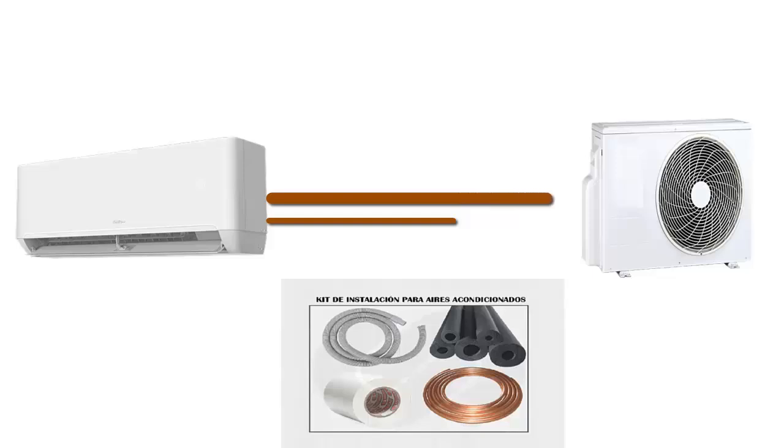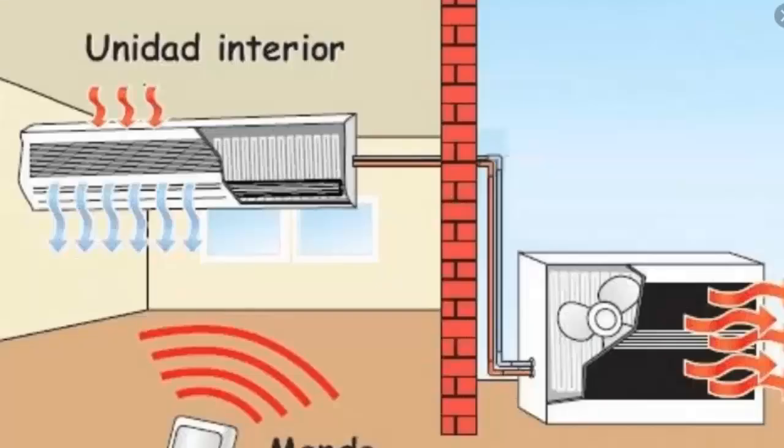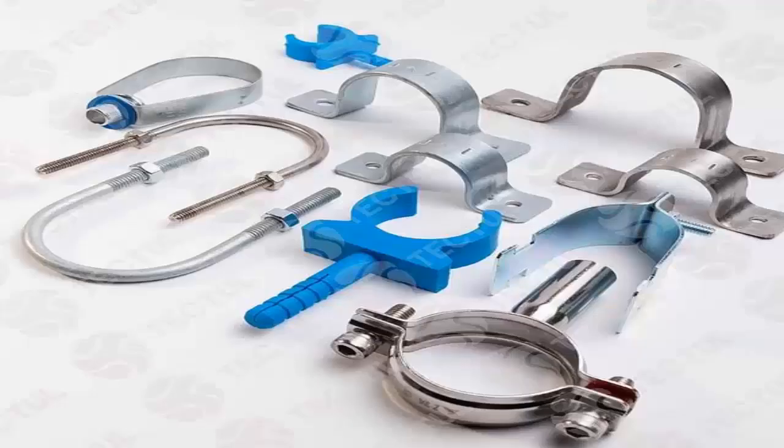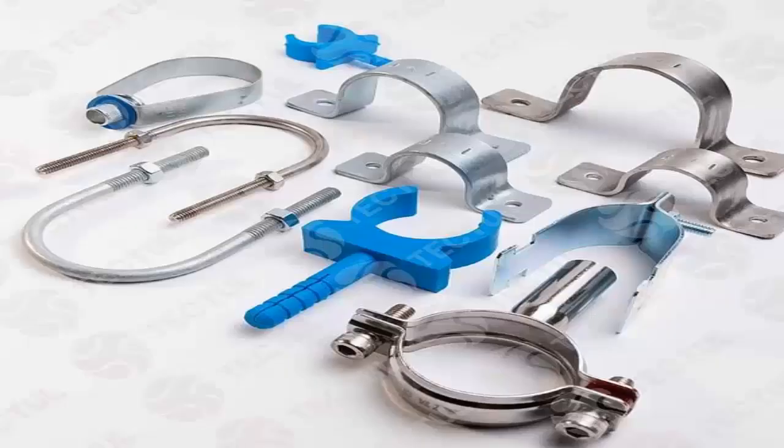7. The best location for the air conditioning unit is one that allows the shortest distance between the indoor and outdoor units, ensuring optimal heat exchange for both units. This minimizes pressure losses and improves system efficiency. 8. Firmly support the refrigerant lines at regular intervals to prevent sagging and vibration, which can damage the lines or cause leaks. Proper support helps maintain system integrity.